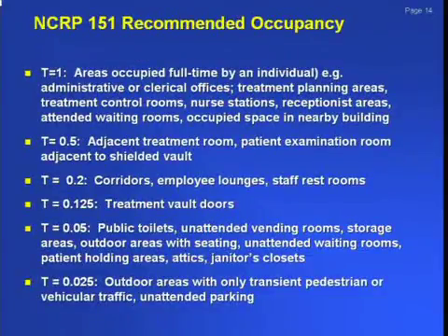What are the recommended occupancy factors? Well, T is 1 for any full-time occupancy, whether it's public or controlled occupational personnel. If it's truly an occupied area, you assume it's fully occupied. The recommended occupancy for an adjacent treatment room, which obviously is very common in a therapy department, is assumed to be 0.5.